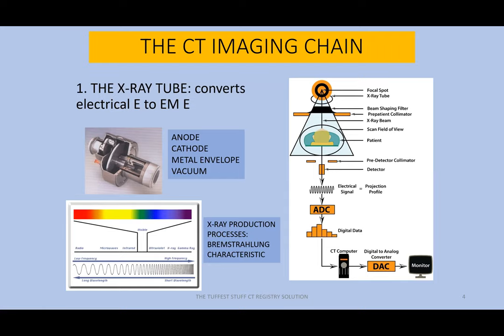Because of the vacuum — as long as it's maintained — there'll be an uninterrupted flow of electrons from the filament to the target in the X-ray production process. That can only happen in the presence of a vacuum. In the X-ray production process, it's normal for things to get very, very hot, especially at the surface of the anode. When that happens, certain impurities get liberated from the metal, become gaseous, and they violate the vacuum over time. Those gassy molecules become a factor when the bombardment of the target occurs from the flow of electrons. If molecules are in the way, it takes away from the energy of those projectile electrons and the beam will not be as energetic.